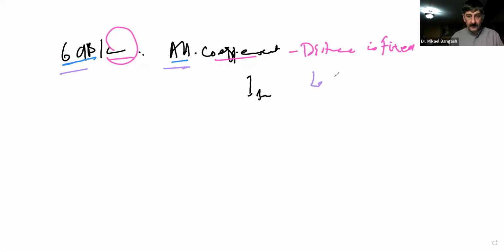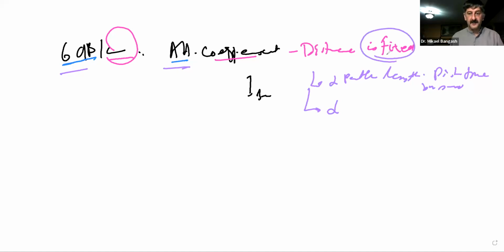Now, attenuation is directly proportional to 2 factors. One is what we call path length, or the distance traveled by sound. But when we say attenuation coefficient, that distance is fixed at 1 centimeter. Did that make sense? Yes. Good. The other factor is frequency, and attenuation is also directly proportional to frequency.